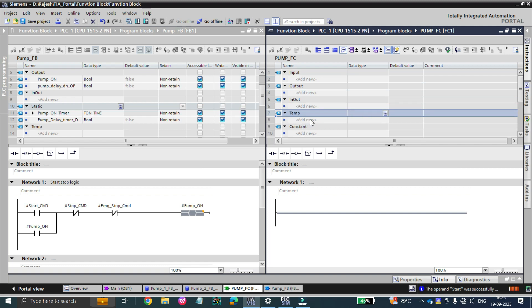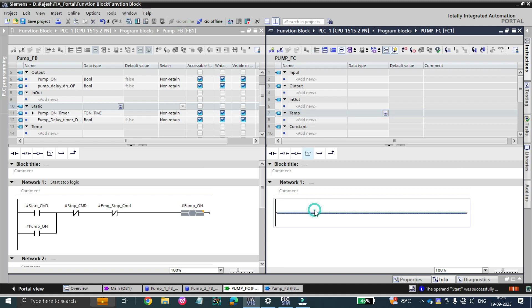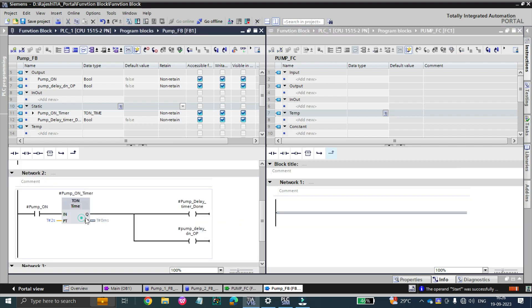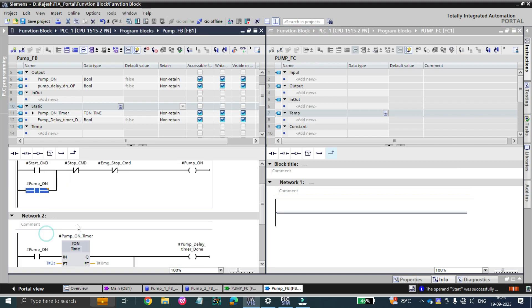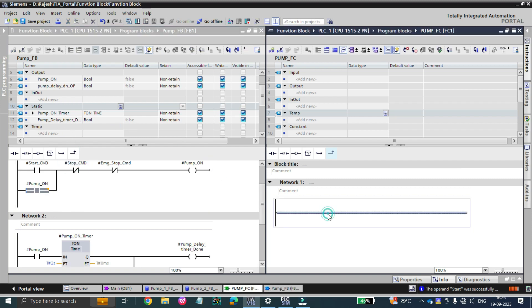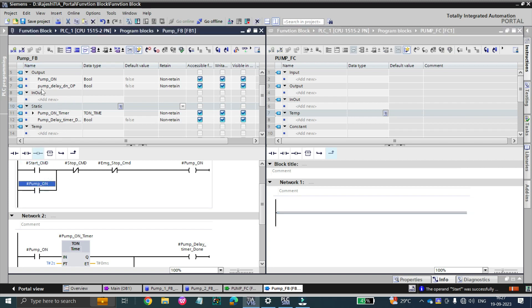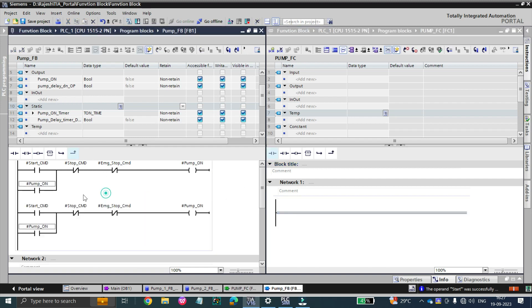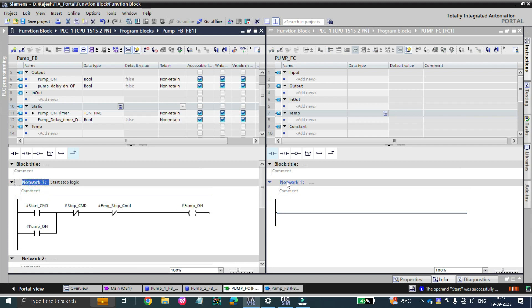In function you only have temporary values — temp — which are not useful for our purpose. What happens in a function is that the PLC scans it only a single time, and because it doesn't have memory it will not store your last state or properties. In a function block, timers and internal values can be stored internally. Those memory bits can't be stored internally in a function — they have to be global.